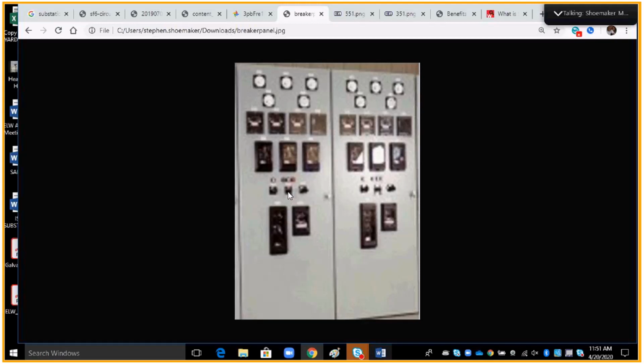I know it's very hard to see by this video. Well, what happened? One of my lights burned out, and it does. They do, especially the red one, because the red one is supposed to be on all the time. That means we have power. Right above the handle, they have what they call a semaphore. It's a flag that's mechanical. When I turn it to the right, a green flag will come up in here, and when I turn it to the left, a red flag will come up in here also.